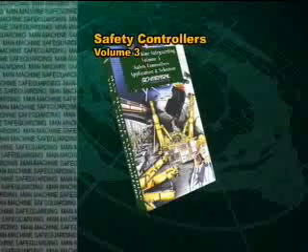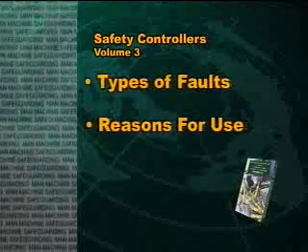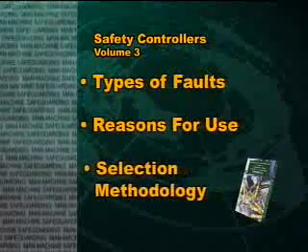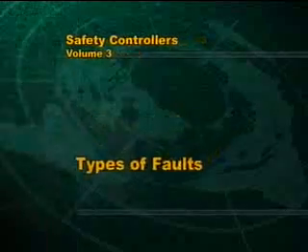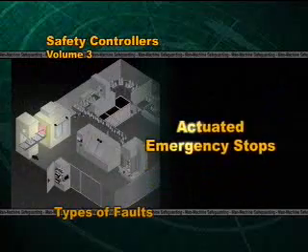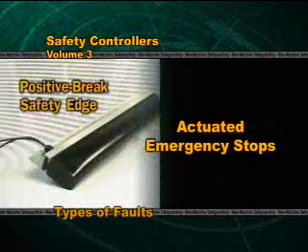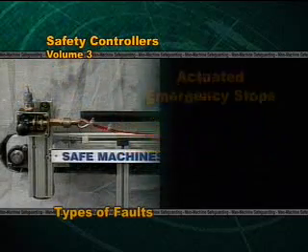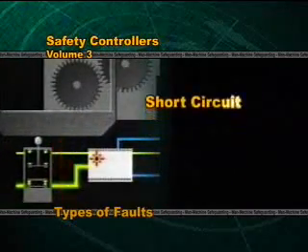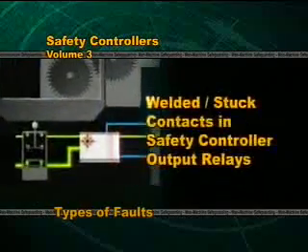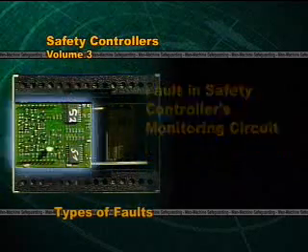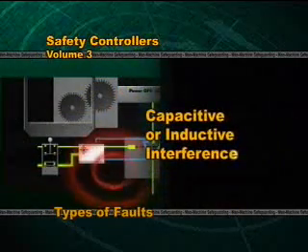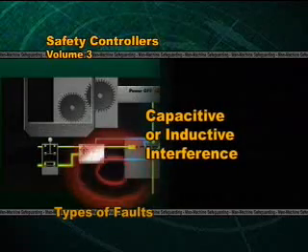Now let's explain the types of faults that a safety controller can detect and the reasons and applications where their use is recommended. We'll start by examining the types of faults that can occur in a safety system. These include open or misaligned machine guards; actuated emergency stops such as light curtains, pressure mats, safety edges, cable pull switches, or emergency stop stations; an open circuit; a short circuit; a short to ground; welded or stuck contacts in the safety controller's positive guided output relays; a fault in the safety controller's monitoring circuit; inadequate supply voltage; and capacitive or inductive interference on the safety controller's inputs or supply voltage.